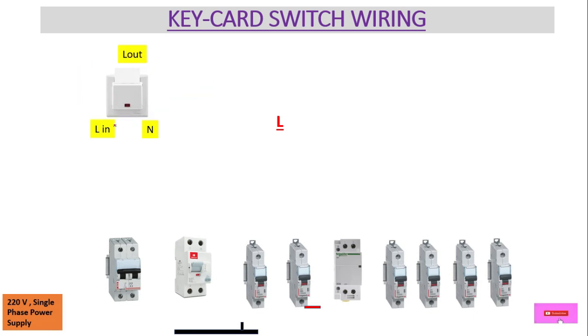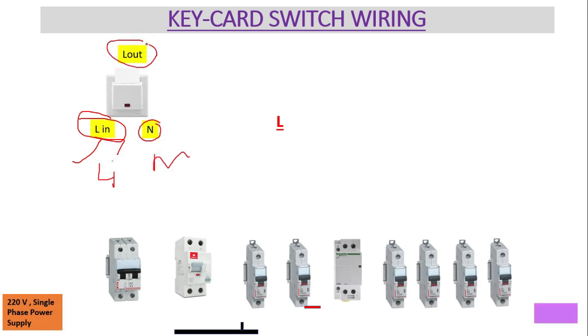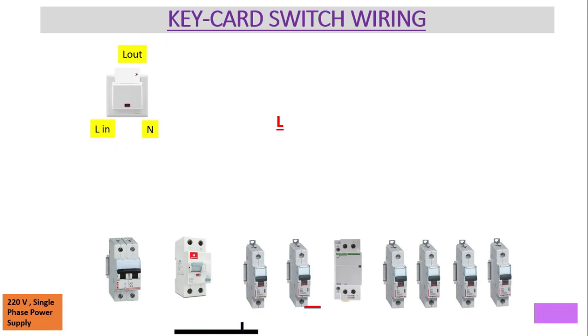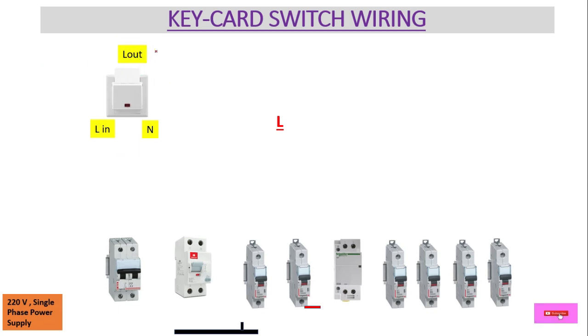Here we have the key card switch, as you can see. It has three terminals: L-IN where the phase or live wire is connected, N for neutral, and L-OUT which is the output from the key card switch. When we insert the key card it provides power to the L-OUT terminal; when we remove the card there is no power at the L-OUT terminal.